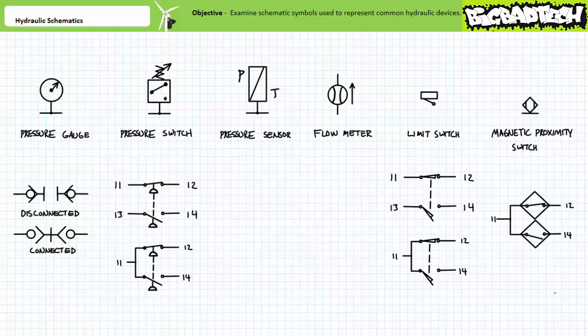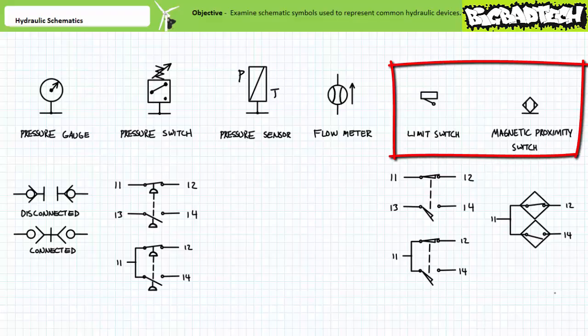Limit switches serve to monitor the physical position of hydraulic actuators. Limit switches come in two notable forms: physical limit switches that must be physically struck to actuate, and magnetic proximity switches that do not require physical contact to actuate. If limit and magnetic proximity switches are employed in a hydraulic schematic, they will most likely use these schematic symbols. This is the one occasion in a hydraulic schematic where diamonds don't mean a fluid conditioning device. The diamond for a magnetic proximity switch means it's a solid-state device composed of no moving parts.